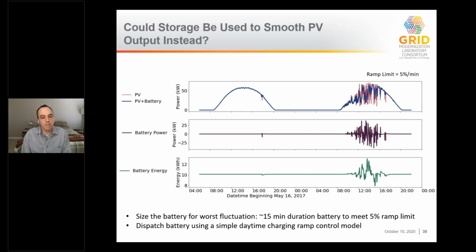So alternatively, we've also evaluated an often discussed strategy of instead trying to smooth the PV ramps directly at that individual plant level using storage. So here you can see how we simulated the operation of a battery that's used to limit these ramps from an individual PV plant. And on a partly cloudy day, that's on the right-hand side there, you can see that the battery has to be rapidly charged and discharged in order to limit the ramp that would come from the PV and battery system. And in this case, we designed the battery to try to limit that ramp to about 5% of the PV capacity per minute.